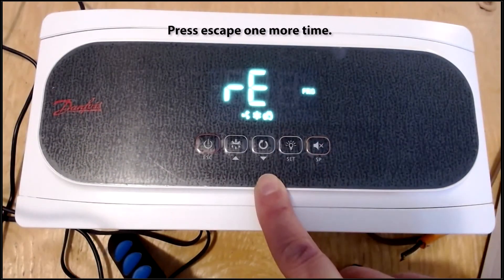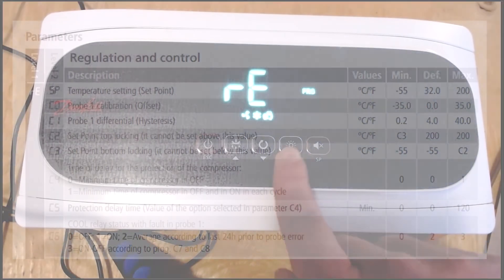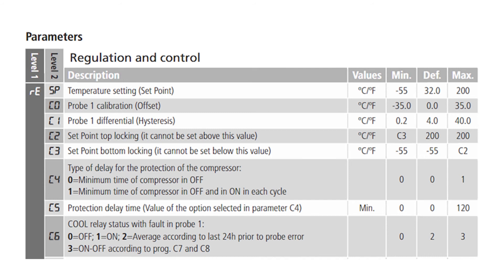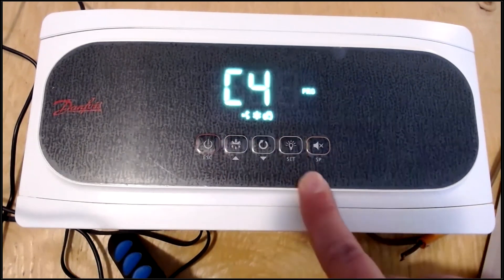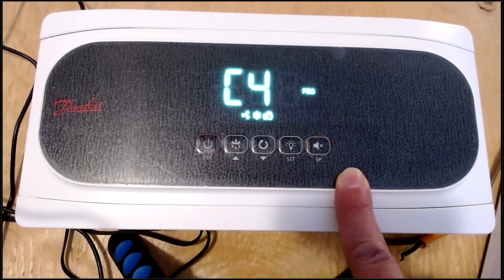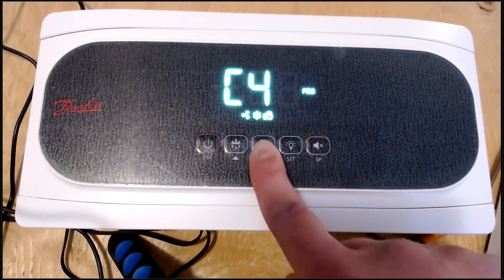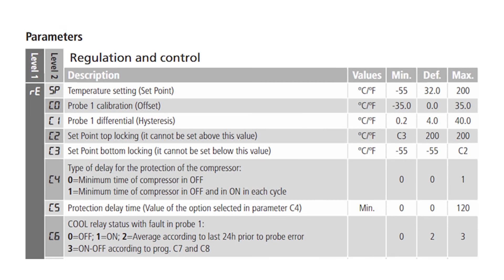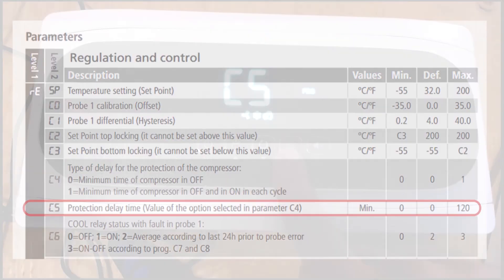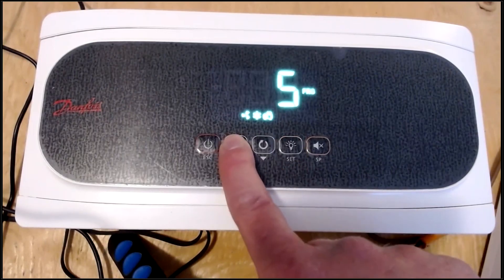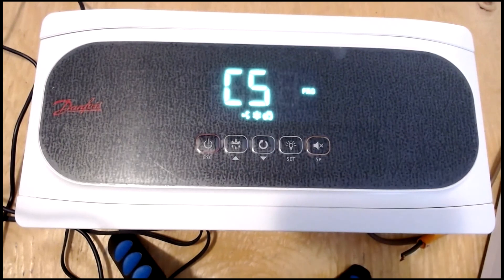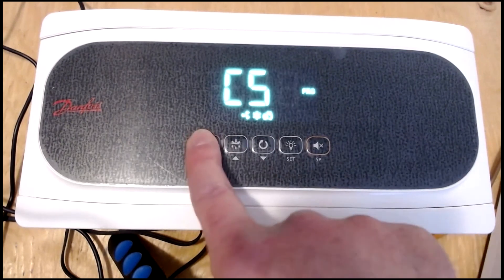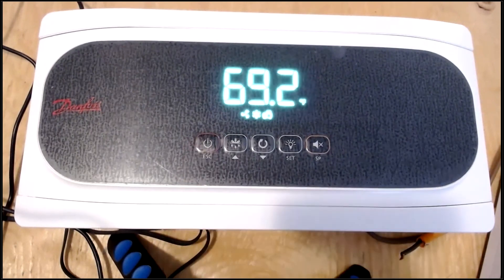Finally, to set the minimum off and on time for the compressors, we will need to scroll back to RE and hit set. From there, we will scroll to C4, hit set, and then select one so that we apply the next values to both the minimum off and on runtime of the compressor. Once we've done that, we scroll to the actual value itself, C5. Hit set and since we selected 10 minutes, we need to scroll to 10 and hit set. Once we've done that, hit escape twice and we go back to the temperature control menu.